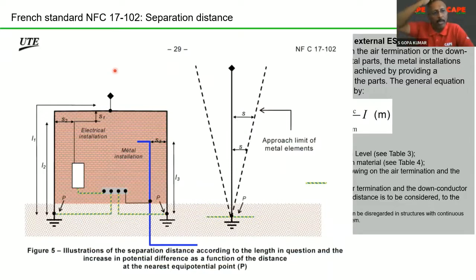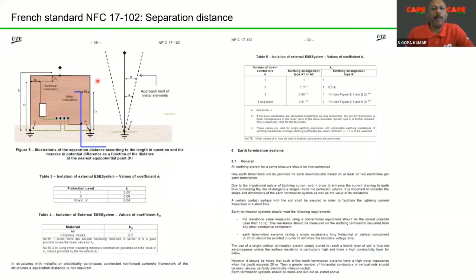But my question to the clients, the people who are using ESE: I'm sure you must have never considered this particular point. Of course, in conventional lightning protection, as per 62305, in some cases clients ask to neglect separation distance, but we always oppose this, and we sometimes reject the designs or don't offer any solution to them if the separation distances are not calculated. Now, please understand that the same separation distance is applicable for lightning for an ESE standard, the NFC standard, as well. If we apply the same separation distance, you can find the same values.